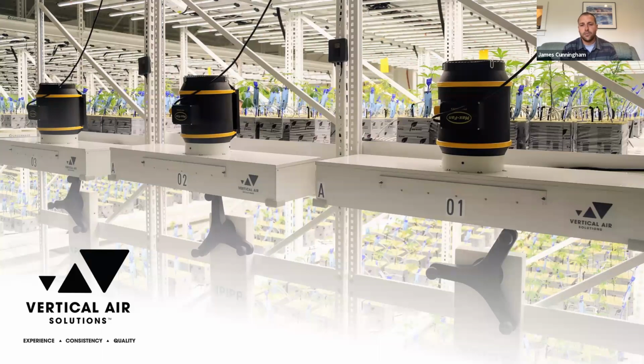So in getting into this space, I realized instantly that we essentially are creating a big cube within the farm. And historically throughout the space, throughout the cannabis indoor horticultural platform, we have been able to control our environments very easily through oscillating fans, strategic supply over a single tier canopy. What the new platform did was create barriers throughout the space. So essentially you're creating 2, 3, or 4 canopies within one room. So essentially this is a cube that you're supplying your environmentals to, but how do you get those environmentals supplied to the inside of this cube, and how do you provide adequate air circulation tier to tier?